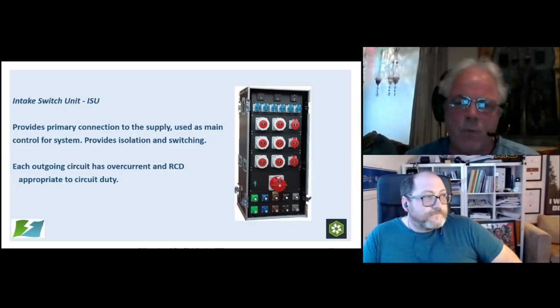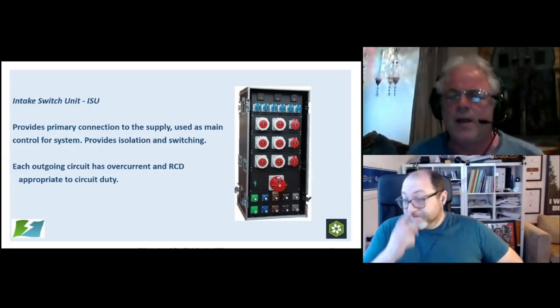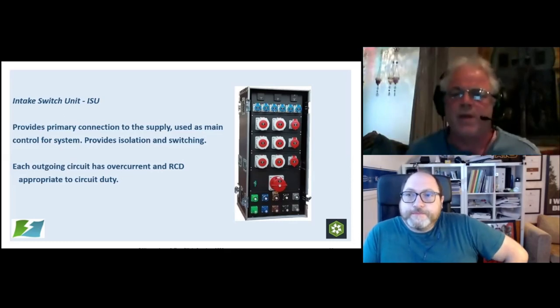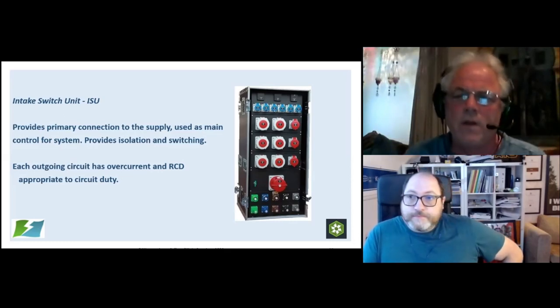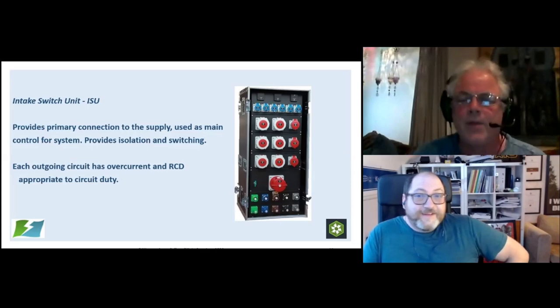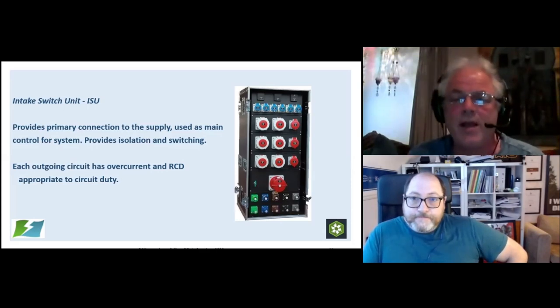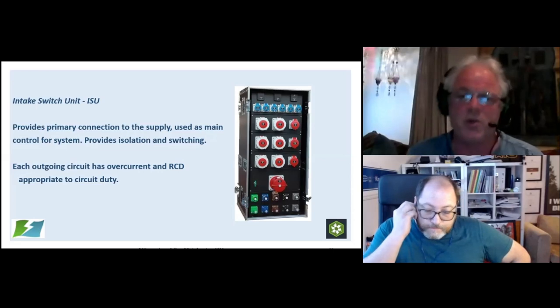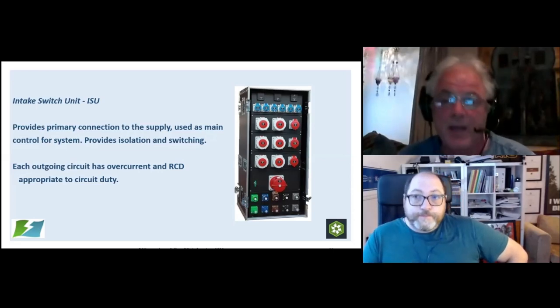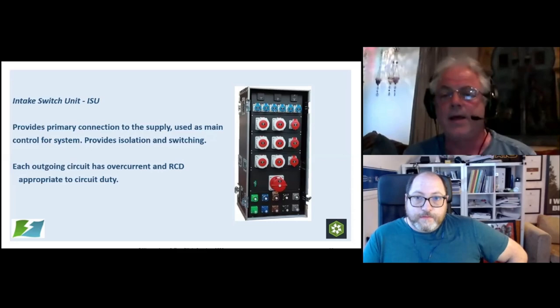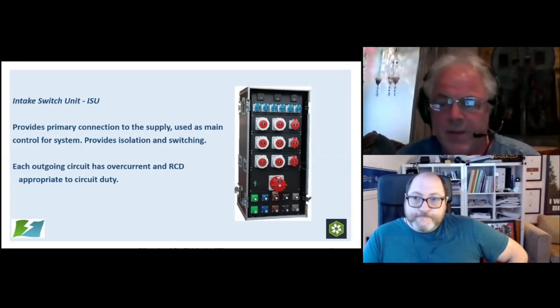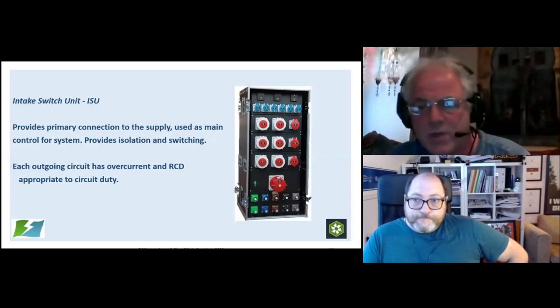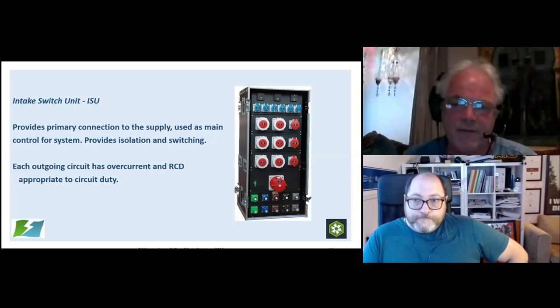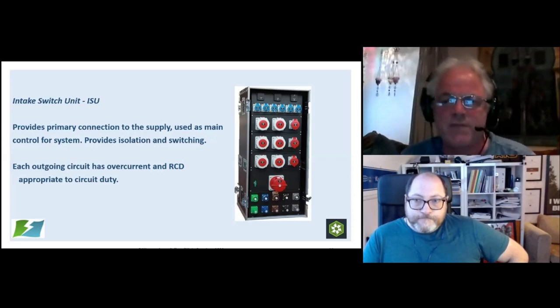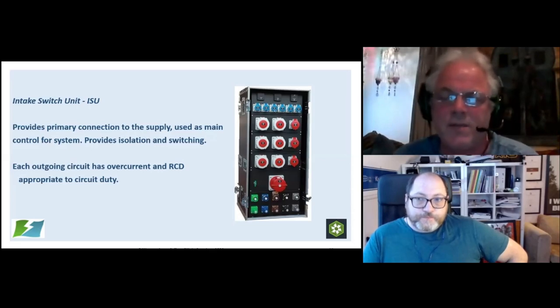And what I like personally, and this is me being a control freak, is I like ISUs with a main switch on that I can actually lock off. That makes me really popular. Yeah. But also they'll have RCD protection on there. RCD protection for your distribution cables. Obviously the RCDs must be selectable, must be time delayed, because you don't want to be putting 30 milliamp RCDs on distribution cables. Quite a lot of ISUs will also have 16 and 32 amp socket outlets for final circuits, and they must be protected by a 30 milliamp instantaneous RCD.